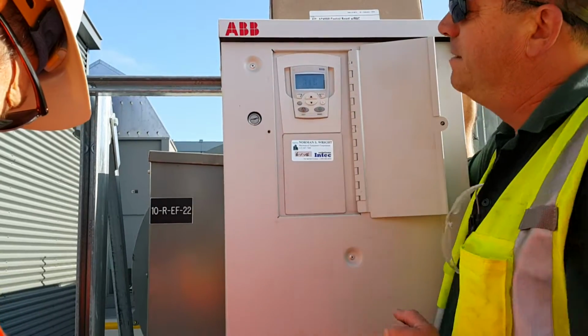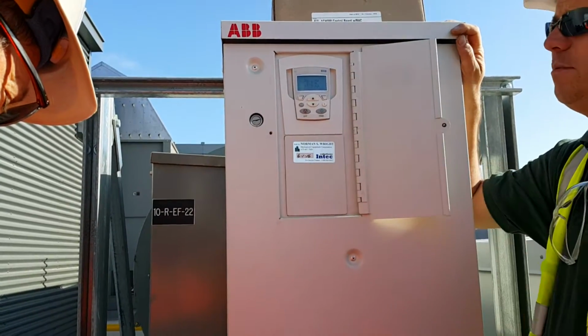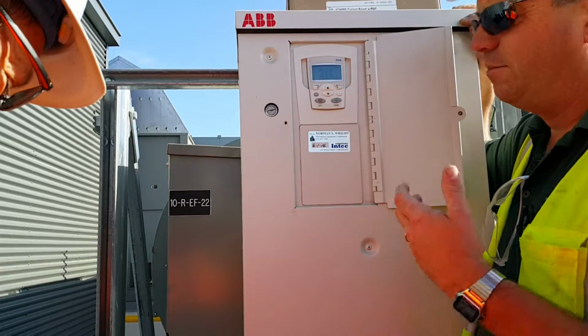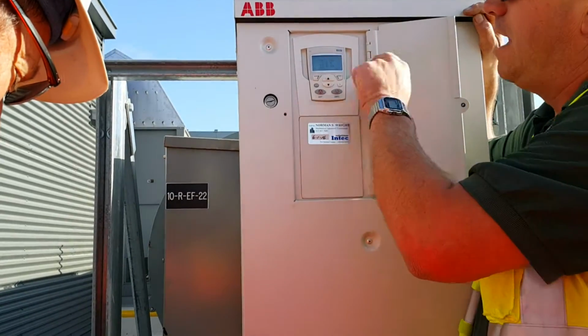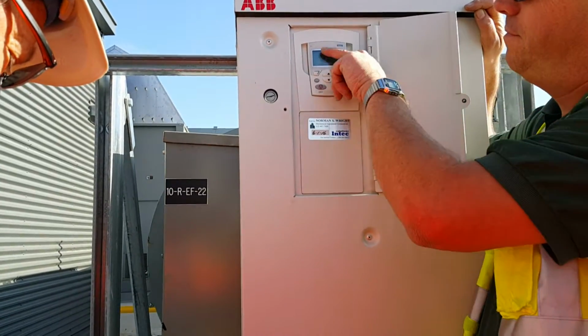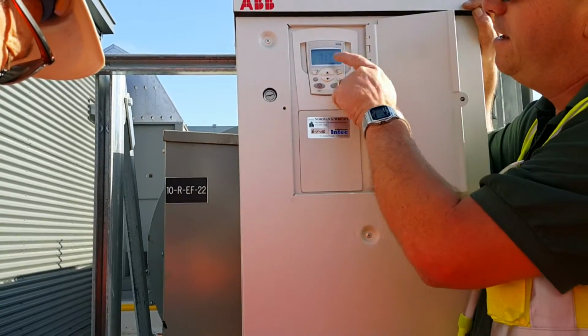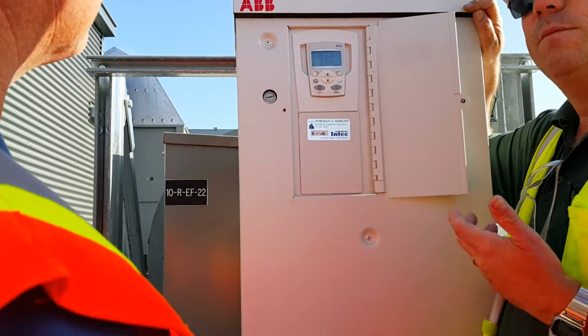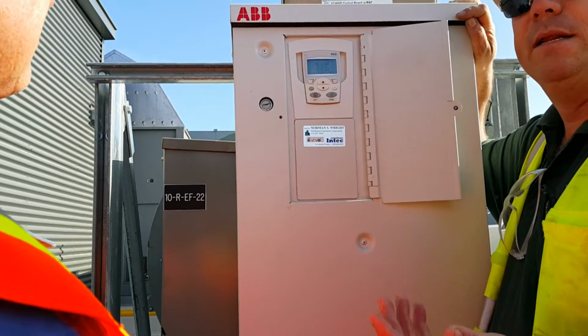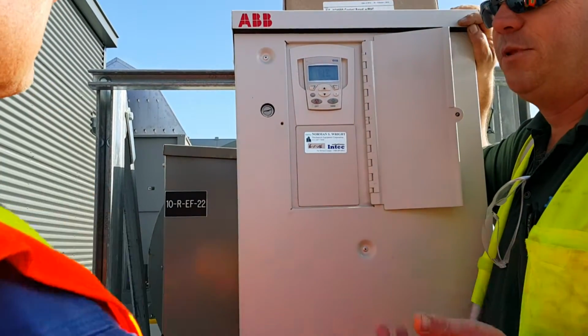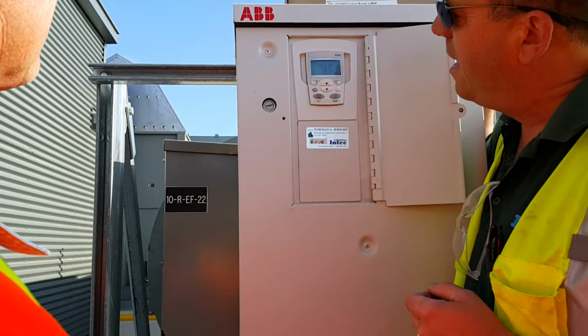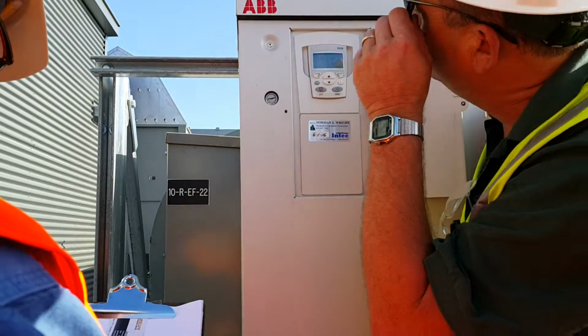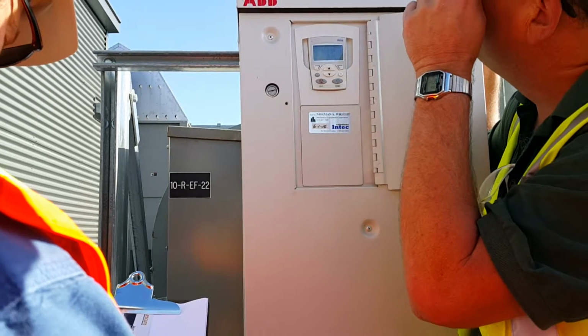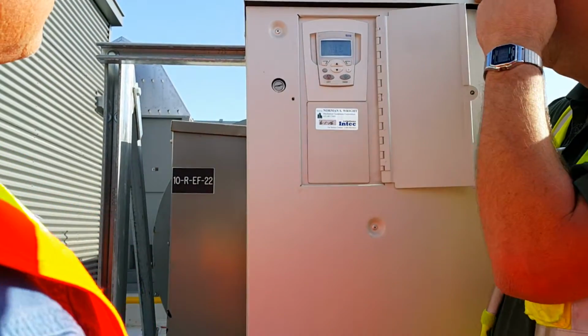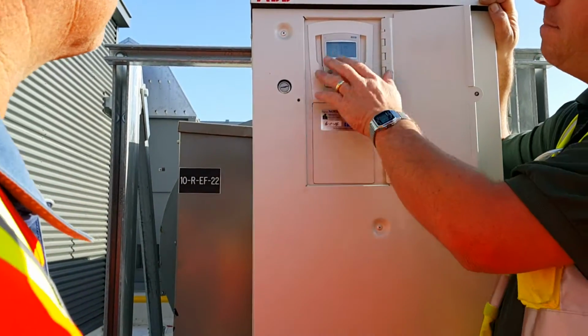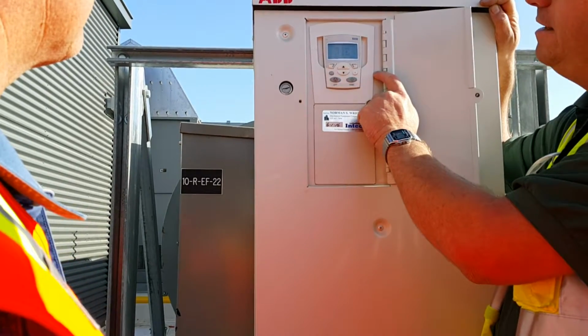We look down here, the three big lines. These are all changeable, but we set them up for you for things that you're most likely to be interested in. The top line is going to be the frequency the motor's running at. The next line is going to be the amperage. And the bottom line is the milliamp signal from the BMS system, which is also your speed control. How many milliamps, between the 4 to 20 milliamp signal, that it's being told to run. In this case, it's right at 12 milliamps. Well, that's why it's going about 30 hertz.